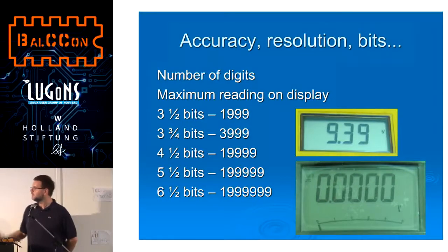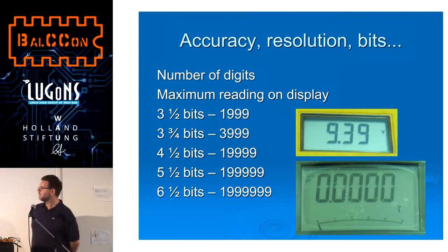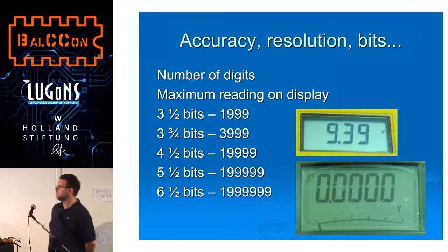What we are changing here is accuracy and resolution. Looking at the specifications of modern multimeters, first you'll see how many digits it has. This yellow multimeter has three and a half digits. That means it can show three whole digits, and the first digit can only be zero or one — we call that three and a half digits. More advanced multimeters have more digits and can show more precise values: three and a half, four and a half, five and a half, or six and a half digits.